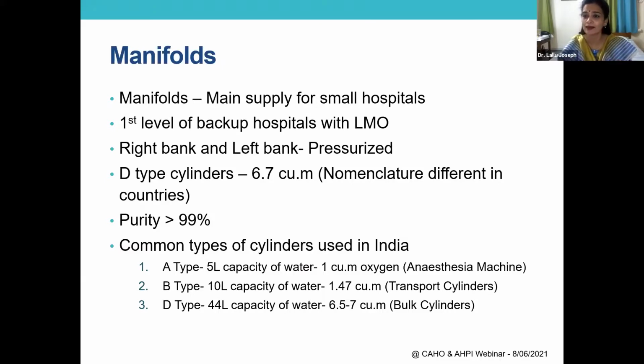The nomenclature, we must realize, is different in different countries. We follow the A, B, C, D system, whereas in the UK, it is JKL. So the D-type cylinders in India are basically the ones that we use in the manifold. The purity is over 99% because the liquid from the LMO is typically converted into gas under pressure and it is filled into this particular cylinder.